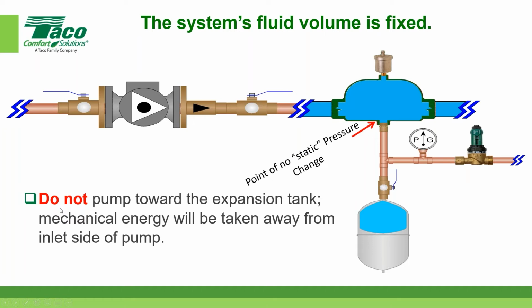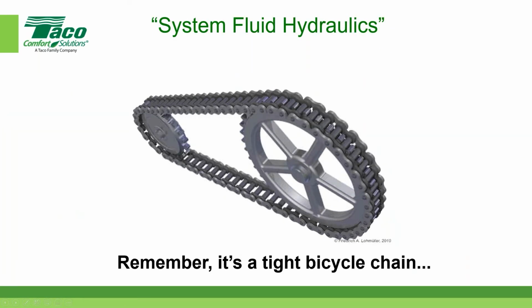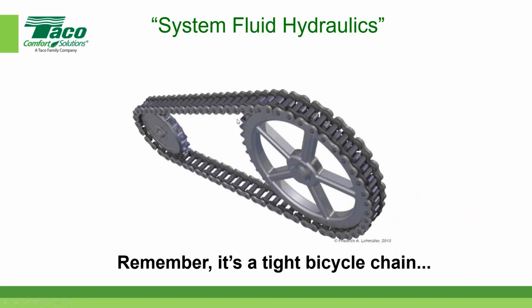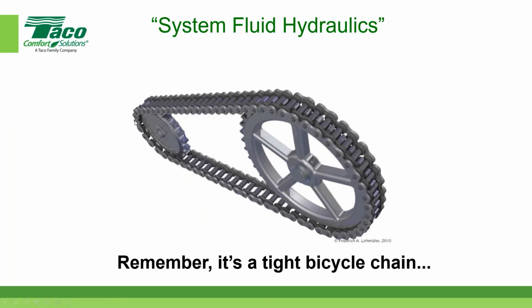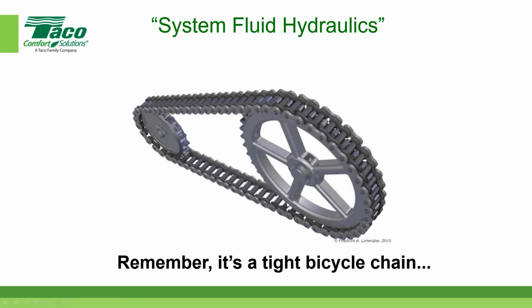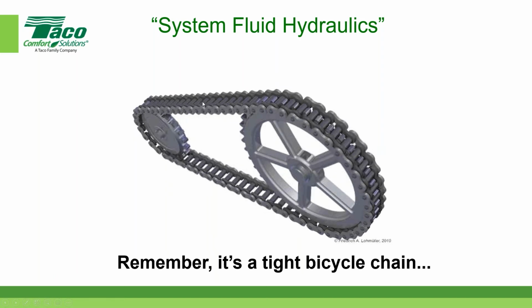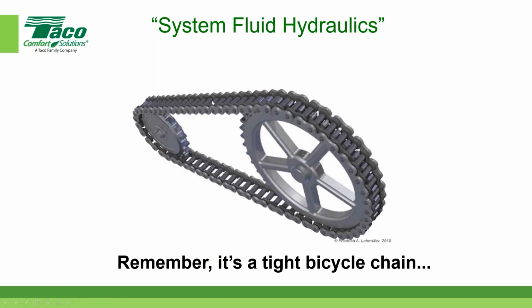So that's why we're telling you, don't pump toward the expansion tank. All the mechanical energy that circulator adds is going to be taken away from the inlet side of the pump. Remember, this is a lean, mean, black and green pressure differential machine. It's going to create a pressure differential, but if it can't put it downstream of the circulator, it's going to pull it backwards, or pull it down on the inlet side of the pump, which is usually not desirable. Okay. And remember the same analogy I told you. If the water in the system is likened to links in a chain, then where would those extra links come from in order to go down that pipe and change the pressure on the gauge?